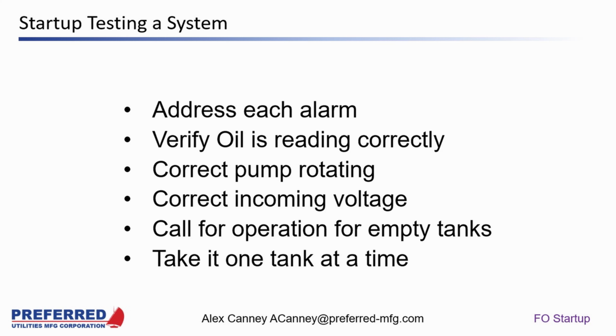And that's where I can then begin to isolate and take it one tank at a time. You never want to do all of them at the same time because you put an undue stress on the system unnecessarily, when you want to verify that each one of the day tanks works properly in all their different functions. Well, if you have 4 or 5 day tanks, it can be hard to know if everything doesn't go perfectly, and startup is the time you want to find that out. If multiple things are happening at once, it can be hard to really isolate those variables. So it's a really good point, trying to do it step by step so that if something does go wrong, you immediately know what the culprit is.